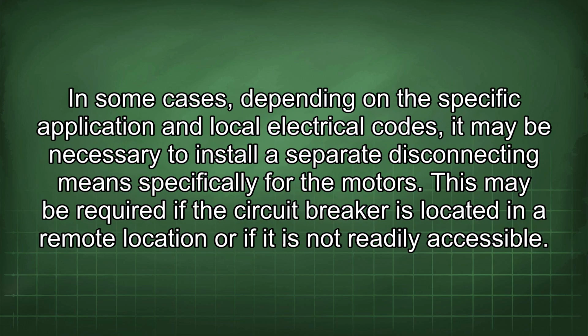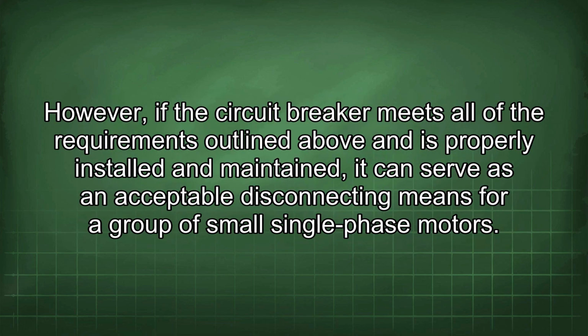In some cases, depending on the specific application and local electrical codes, it may be necessary to install a separate disconnecting means specifically for the motors. This may be required if the circuit breaker is located in a remote location or if it is not readily accessible. However, if the circuit breaker meets all of the requirements outlined above and is properly installed and maintained, it can serve as an acceptable disconnecting means for a group of small single-phase motors.